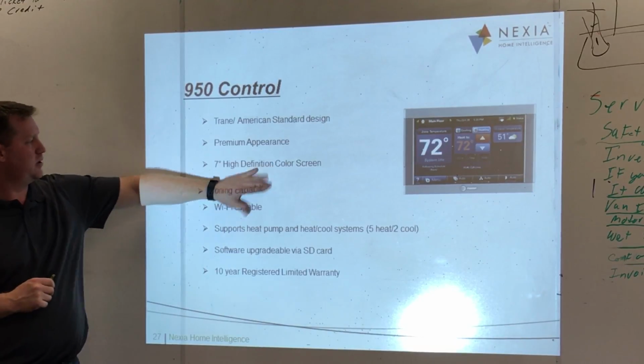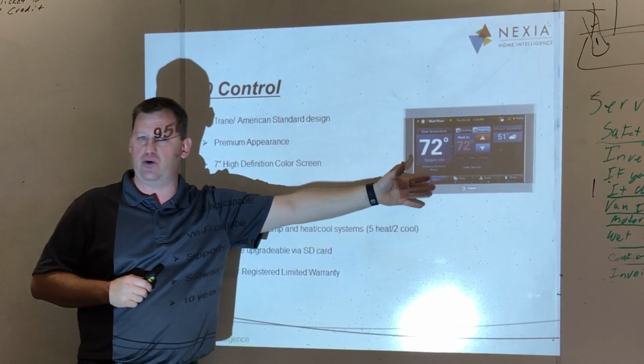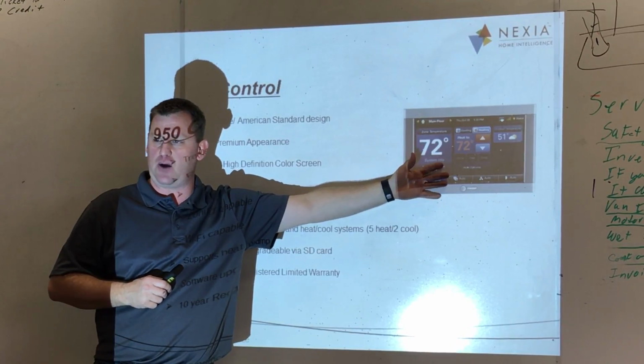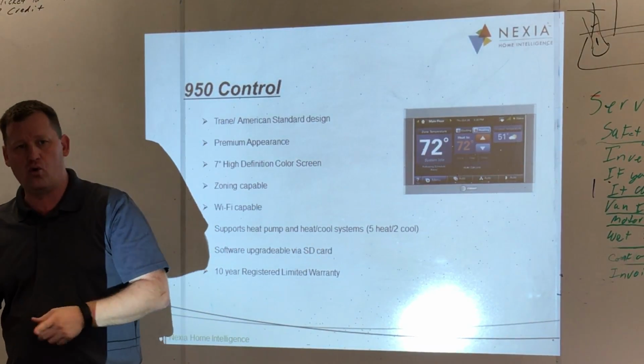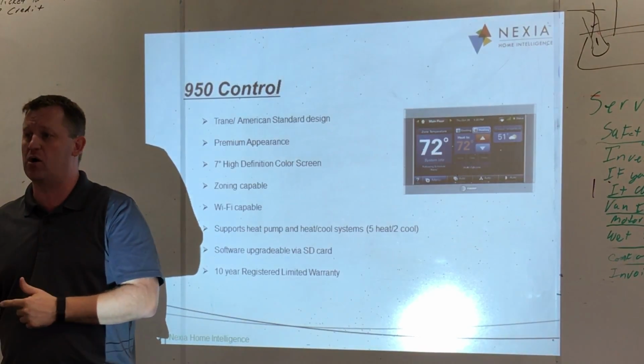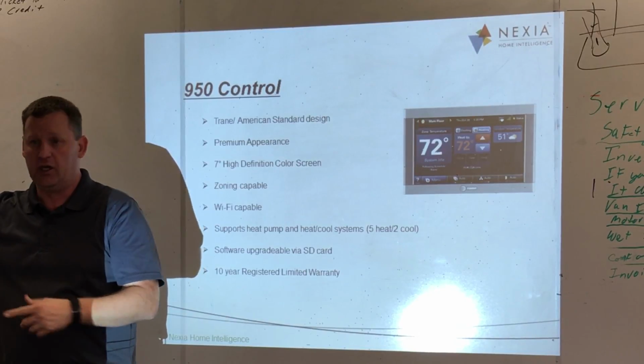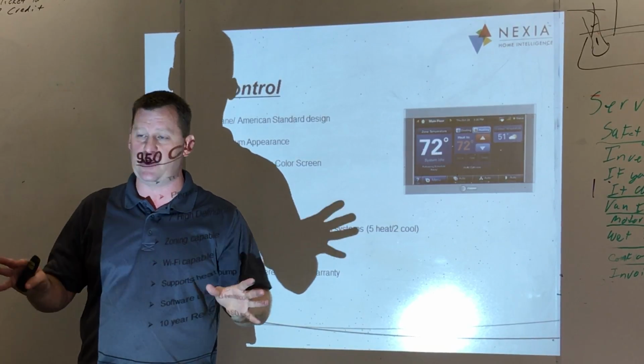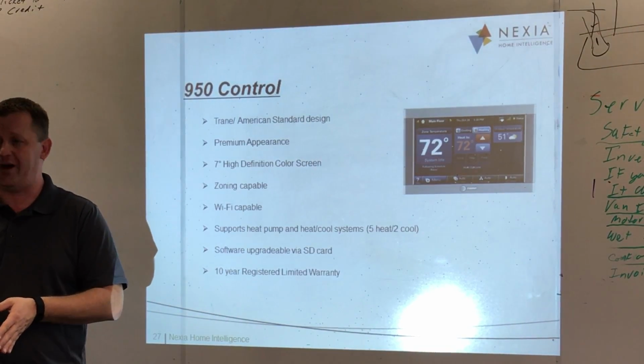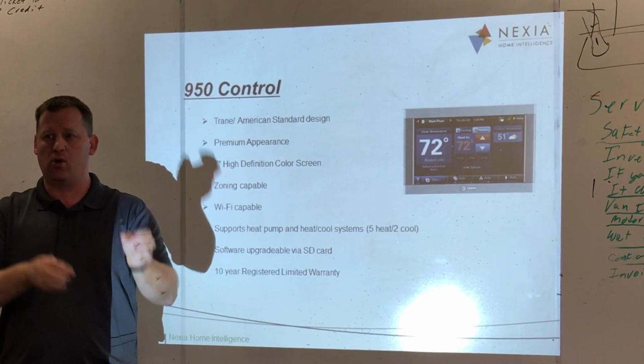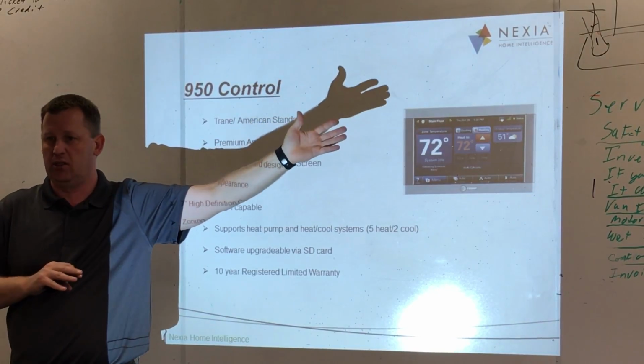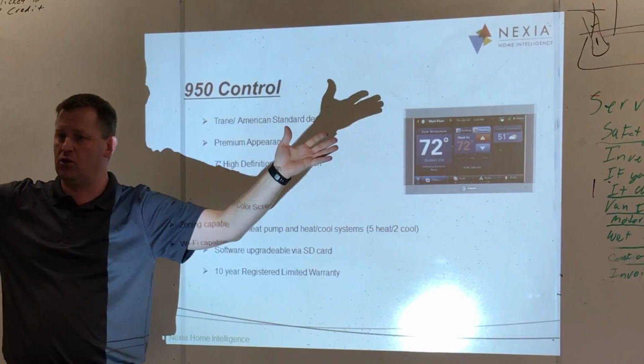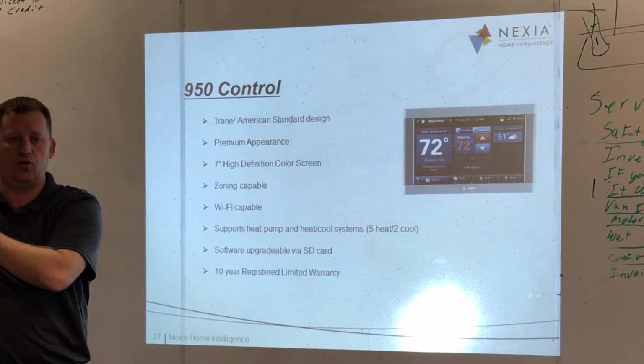All right, so 7-inch screen, this is our zoning stat, right? If we're doing the zoning system, this is the stat we use. Now remember, guys, if you're dealing with an old Trane zoning system and you've got a failed part in that zoning system other than a damper, you're swapping out the whole zoning system. We can't get parts, we can't get stats, we can't get boards. Any of that type of stuff is gone. I don't care whether it's a zone board or the main controller board or the main control stat on that old zoning system. It doesn't matter. All of it's gone. They're not making those parts anymore. You've got to convert it to the new zoning system.